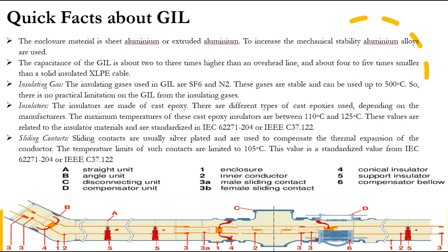Quick facts about GIL: The enclosure material is sheet aluminum or extruded aluminum; to increase mechanical stability, aluminum alloys are used. The capacitance of the GIL is about two to three times higher than an overhead line, and about four to five times smaller than a solid insulated XLPE cable. The insulating gases used in GIL are SF6 and N2 — these gases are stable and can be used up to 500 degrees Celsius, so there is no practical limitation on the GIL from the insulating gases.